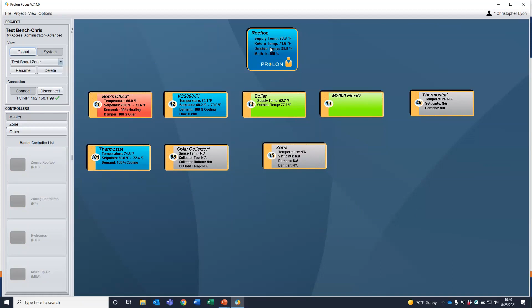But if I want to see what's going on with my rooftop unit, we just double click, and here's my rooftop unit. We can see our outside air temperature. I have a series of input knobs here where I can fake values into this controller just for testing purposes. We can see that our outside air damper is open, probably trying to deal with this high carbon dioxide level. So we can see what's going on with this.